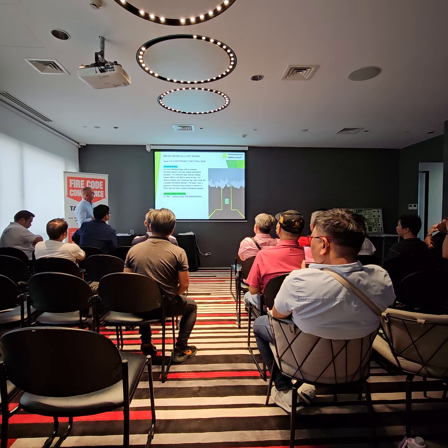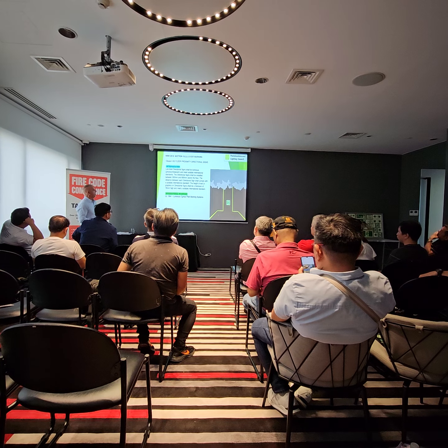Clause A6 is the section. It doesn't actually call it floor proximity directional signs. It's a little bit unclear. But basically, again, we proposed that this is talking about a low level or floor proximity signage system, directional signs and that sort of thing. So as I said, UL 1994 on its own, with no other parameters around it, will satisfy that requirement.